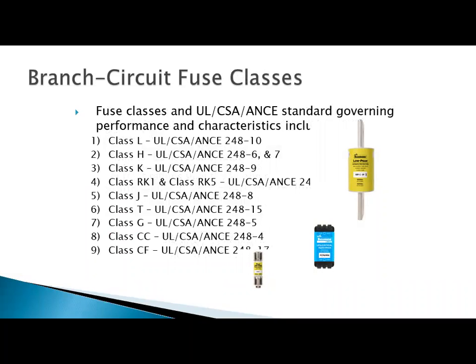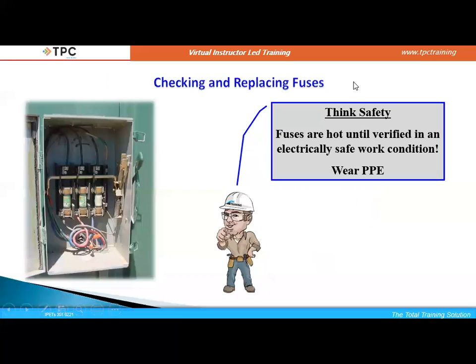So you can see we have different classes of fuses: class L, H, K, RK. A lot of this is going to be determined by voltage and clearing time. And a lot of these fuses can be used in different types of systems, but a lot of it is going to be voltage dependent on what class of fuse you would get. Also, some of these will be current limiting. So a class L fuse is definitely a current limiting fuse, and that is going to help us reduce the amount of incident energy that could be present at that facility.